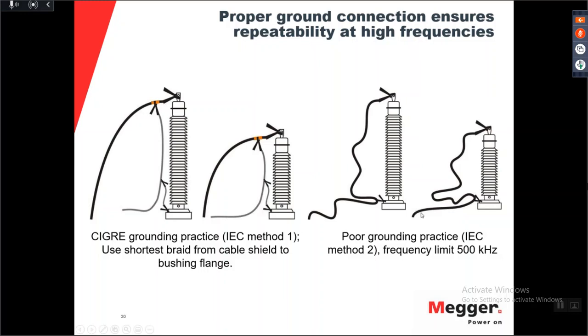Then I also said the shield ground practice. And in the Cigre technical brochure, they recommend method 1, where you have a straight shield ground. So this cable here is grounded, and then you have a connection point here or at the clamp where you can attach a ground braid, and it should be attached here, straight along the side of the bushing. Because if it's not straight along the side of the bushing, you cannot repeat the same measurement setup.